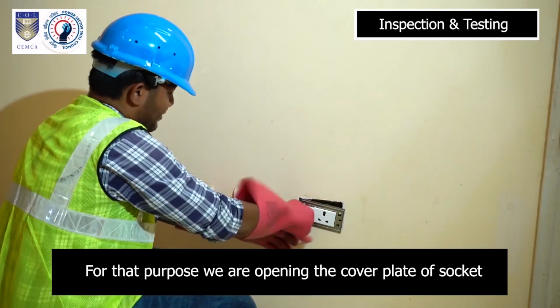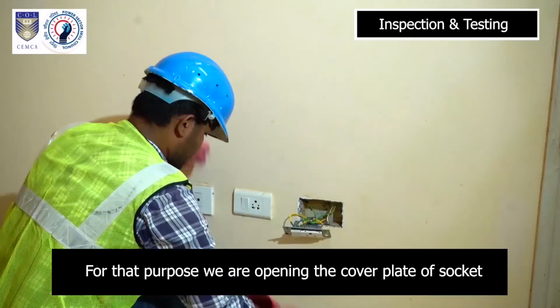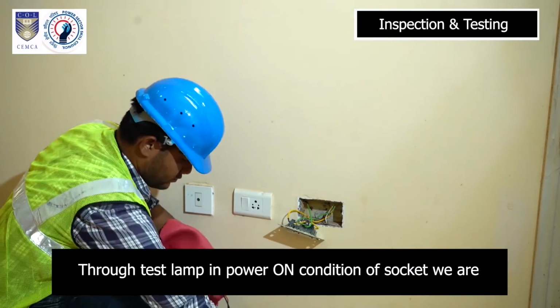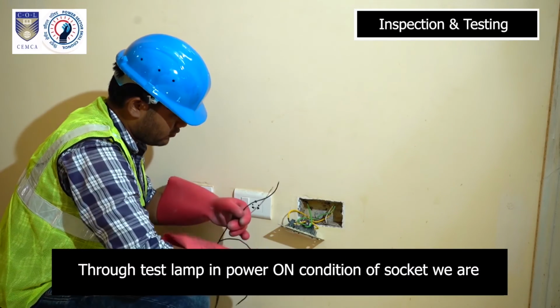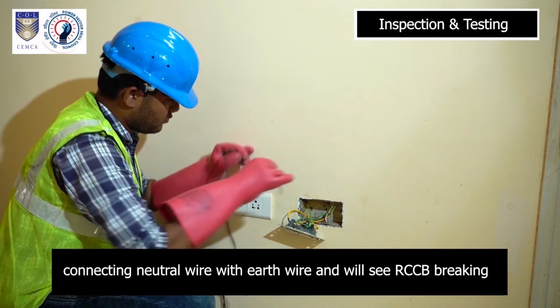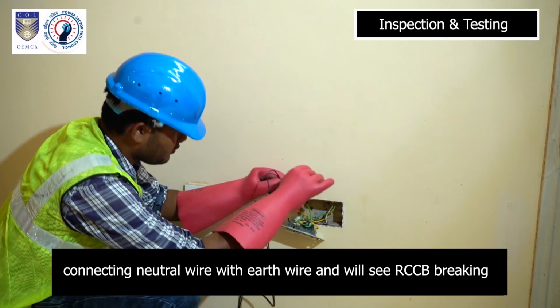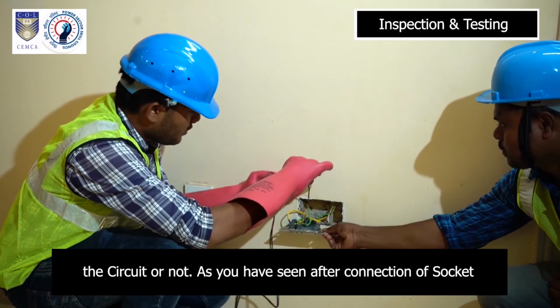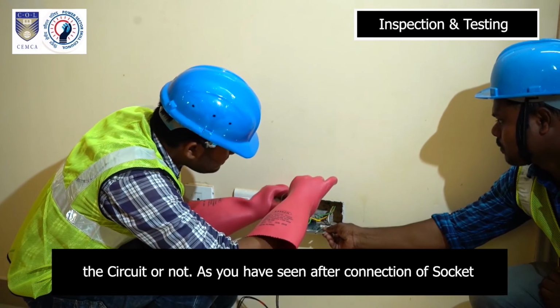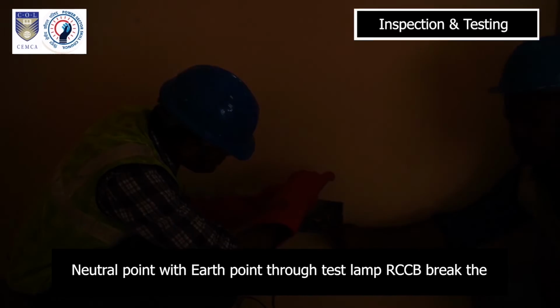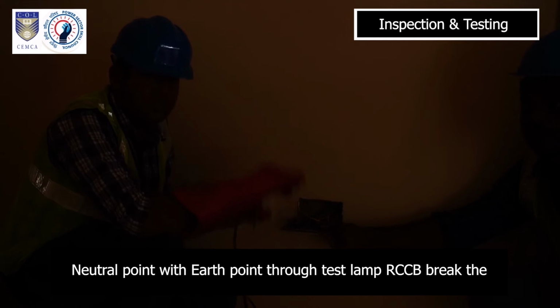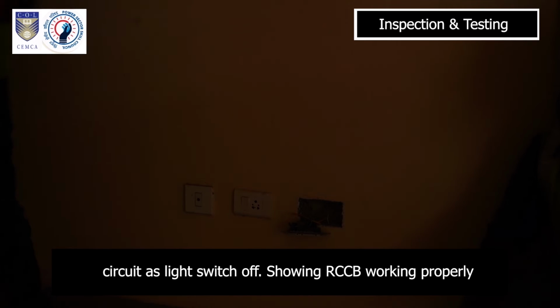For that purpose, we are opening the cover plate of the socket. With the socket in power-on condition, through a test lamp, we are connecting the neutral wire with the earth wire and will see whether the RCCB breaks the circuit or not. As we have seen, after connection of the socket neutral point with the earth point through the test lamp, the RCCB breaks the circuit as the light switches off, showing the RCCB is working properly.